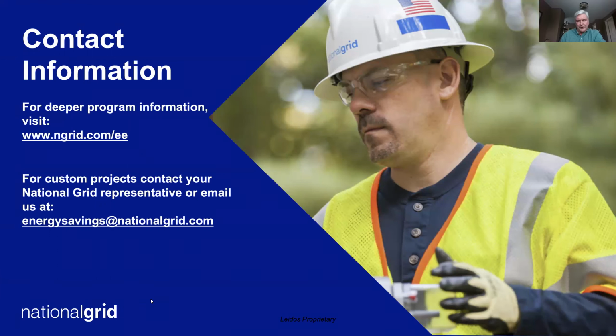Yeah, and certainly you're saving the wiring cost. Some systems might need repeaters to boost that signal. And I will point out that before you go all in for wireless sensors, you want to make sure that your building is capable of doing that. You have computer rooms that might be lined for radio frequency and things like that, so you might want to have them come through and do a survey first to make sure that where you're putting the wireless sensors, they're actually going to be able to get the signal down to the controller.